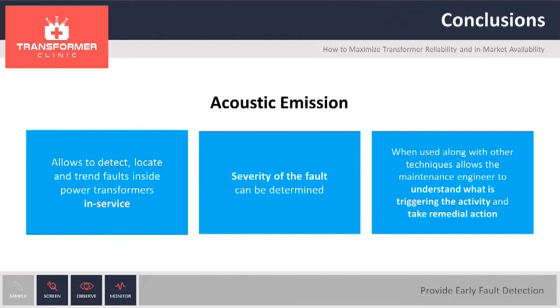Acoustic emission allows you to detect, locate, and trend faults in power transformers with equipment in service. With the grading system, we can give you an idea of the severity of the fault, backed up by 1,500 tests in our database. The main benefit is providing maintenance engineers with a better understanding of what is triggering the acoustic activity, which may help to provide steps to remedy that problem.